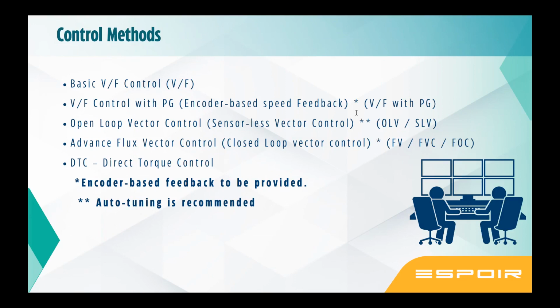cold mode. You need to warm up a bit and then start doing it, because the parameters change drastically when the motor comes to ambient temperature. So you need to do a tuning when the motor is cold to warm, and do it 3, 4 times. It takes the average and then the best result comes out.